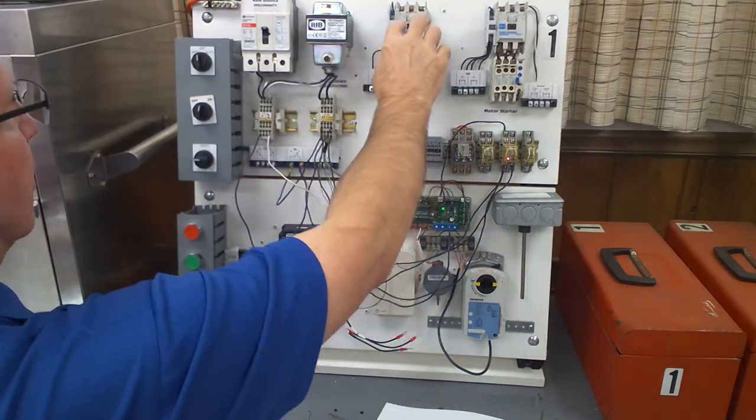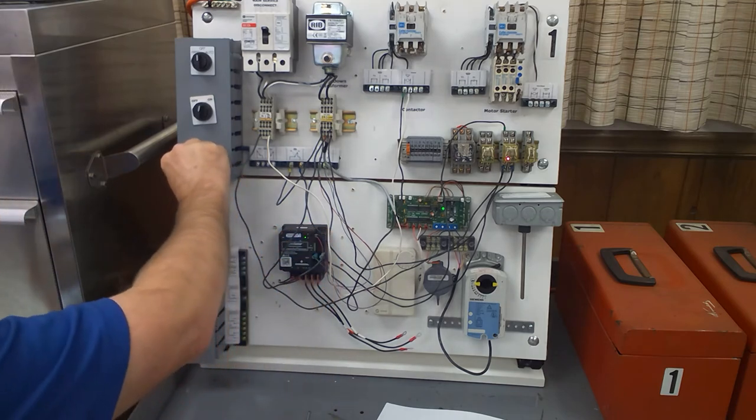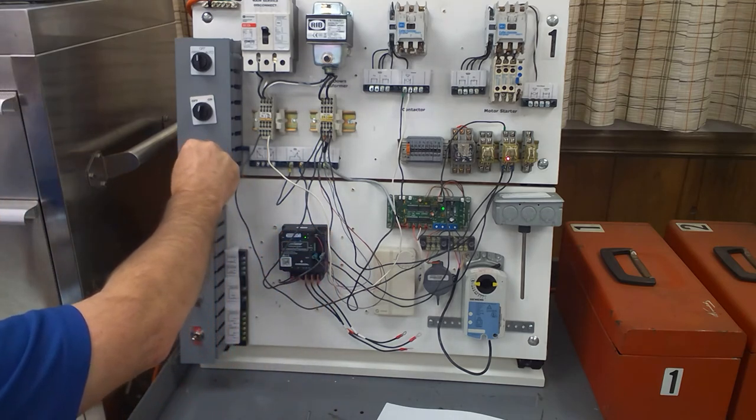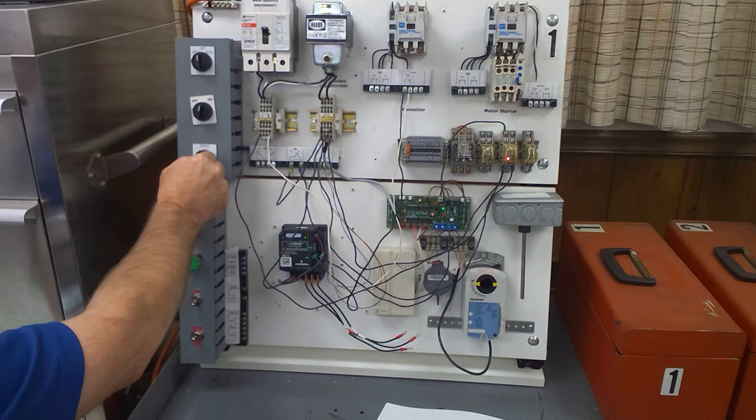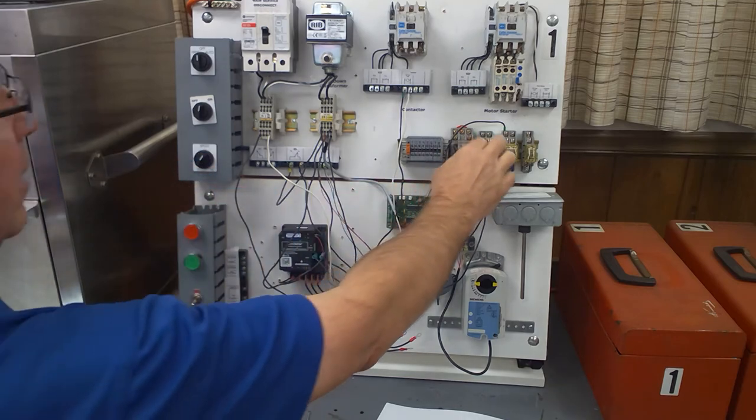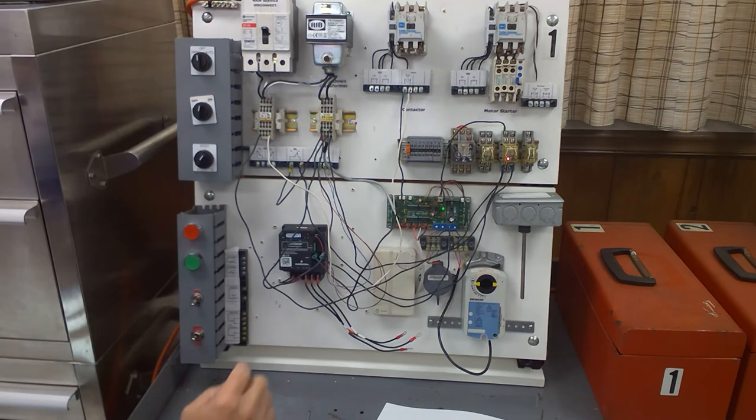So I got a call for cooling, relay pulls in. The core sense says okay, go ahead and start the compressor. Now here is my motor temperature sensor simulator. Once I turn it a little bit above halfway because this is a 10,000 ohm potentiometer, you'll see that I didn't lose the call for cooling, but the contactor did drop out, so it shut off.